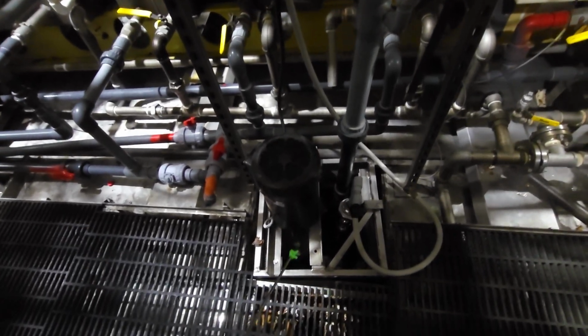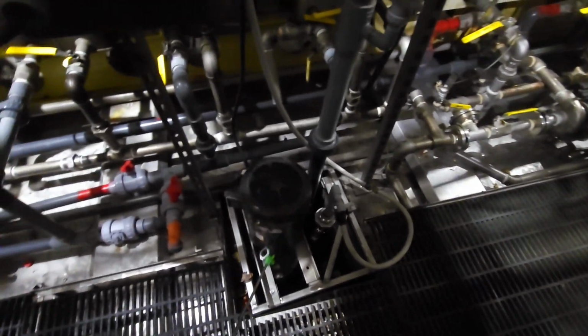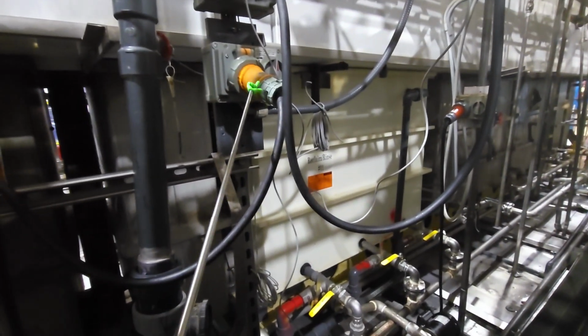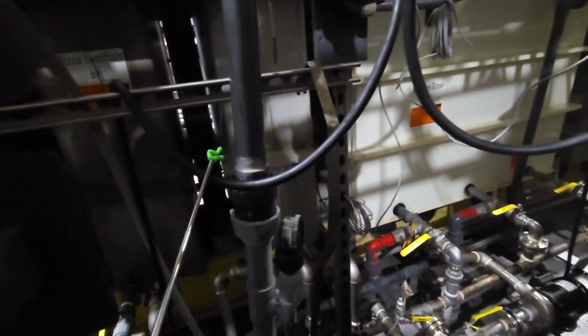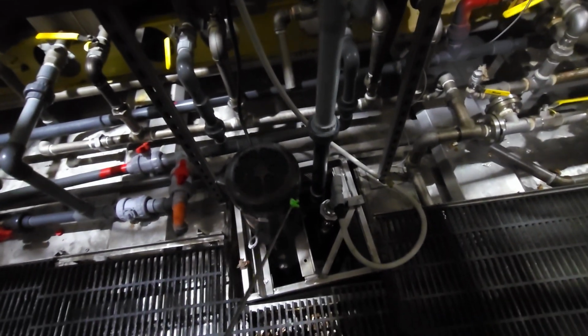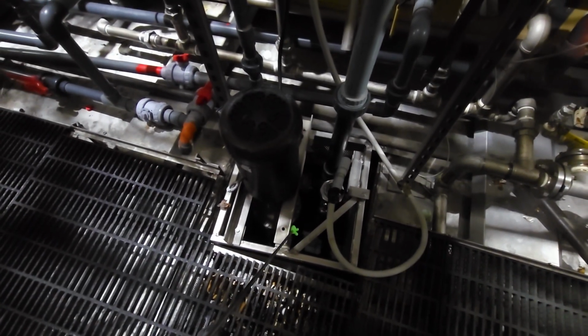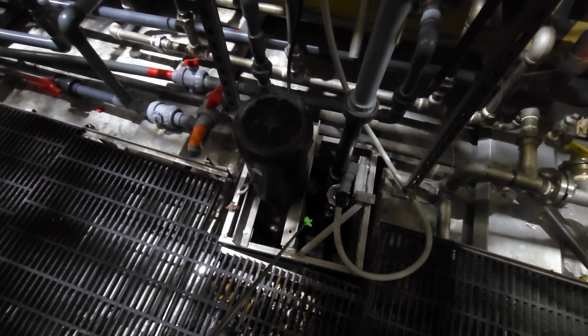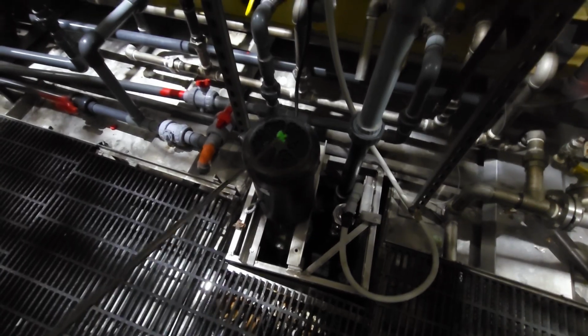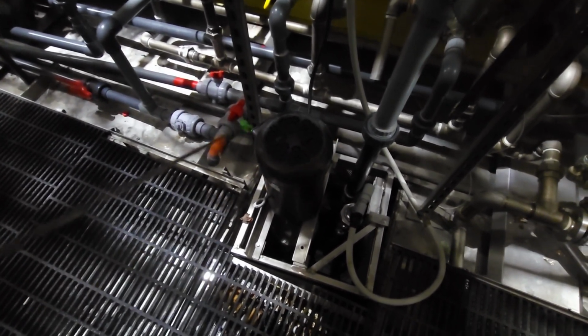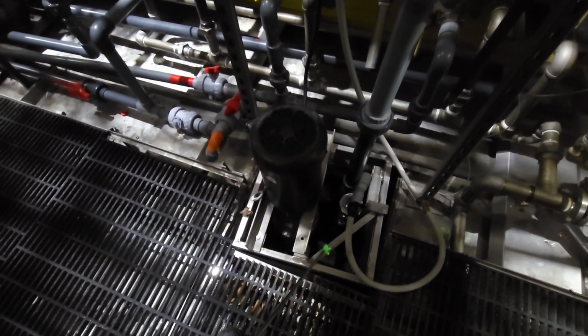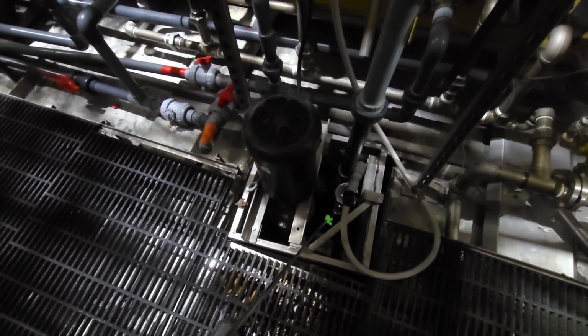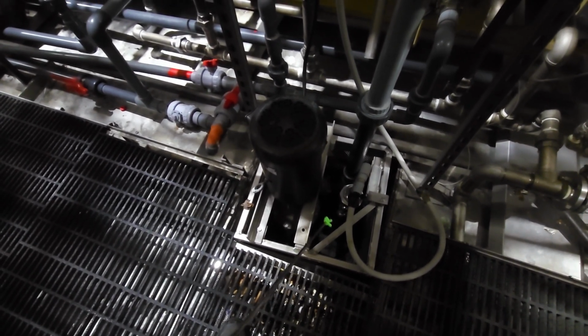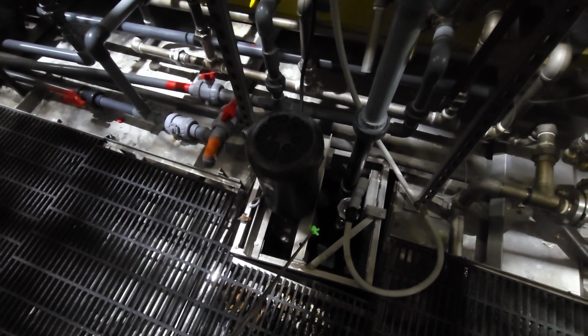Sumps are a simple design. This is a 5 horsepower here. Your power runs up. Always know where your power goes in case you have to shut it off during operation, like you got a leak or something. Down there underneath the water where you can't see, you always have a stinger. The way to know your stinger's missing is if you see that pump rotating all over the place. Your stinger's missing. That stinger takes that centrifugal pump and it pulls it from one point down lower and it balances out your pump.